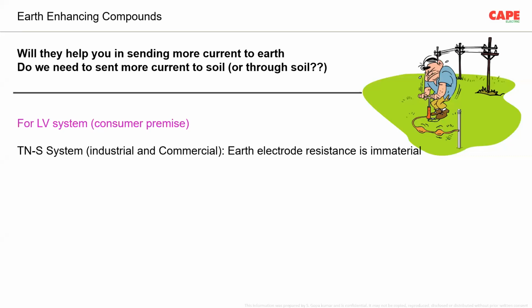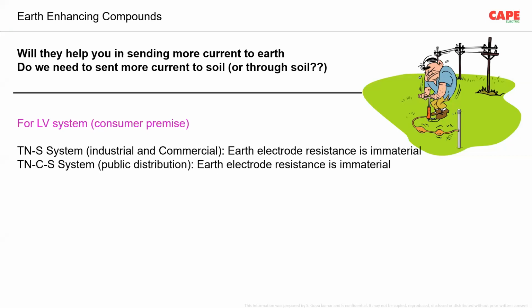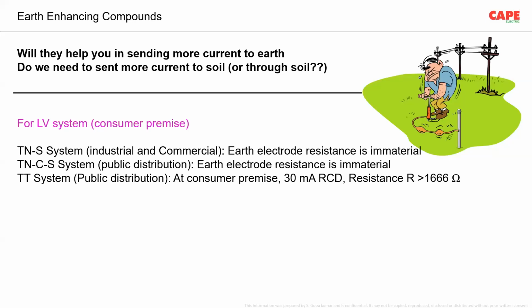Now for low voltage consumer premise. For consumer premise, imagine you have a house or you have a small industry where you are getting 230, 400 volt line. And if you have a TNS system, industrial and commercial application, TNS system, earth electrode resistance is immaterial. In the sense, if the earth electrode resistance is 10 ohm or 50 ohm or 100 ohm, actually it doesn't matter. TNCS system for public distribution, earth electrode resistance is immaterial. TT system for public distribution at consumer premise, if you are using a 30 milliampere RCD, of course, the resistance recommended in the standard is 1666 ohm. You can see it, I think, in table 14.